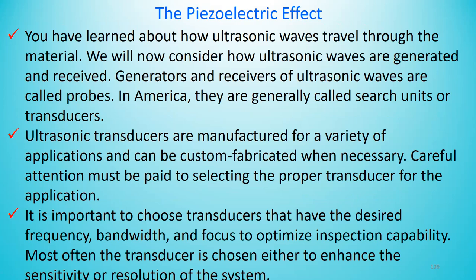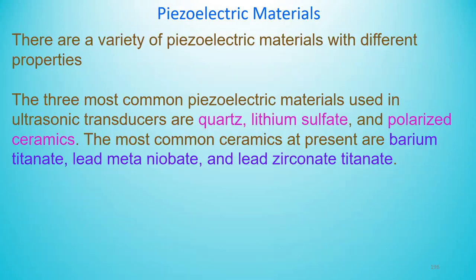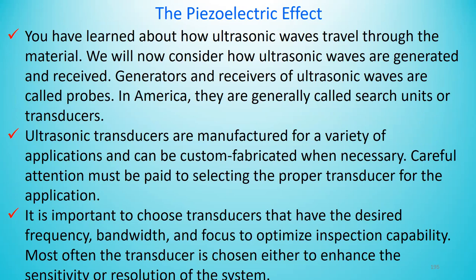Careful attention must be paid to selecting a proper transducer for the application. It is important to choose transducers that have the desired frequency, bandwidth, and focus to optimize inspection capability. Most often, the transducer is chosen either to enhance the sensitivity or resolution of the system.